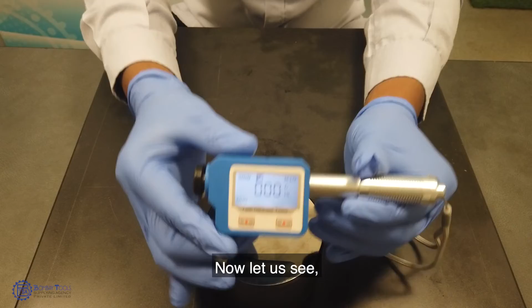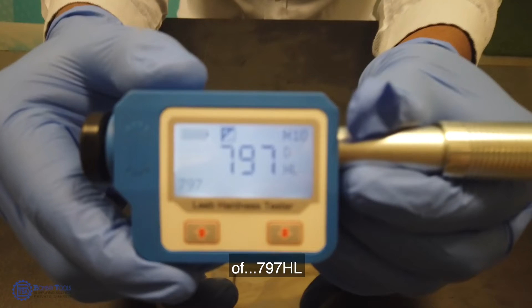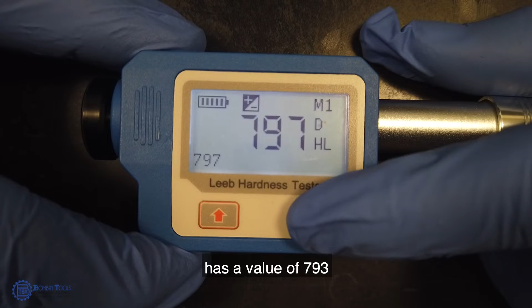Now let us see how to calibrate and use the instrument. We can load the carbide ball by pushing the loading device downward. Then place the instrument on the block and release it by pushing this button. We have got a reading of 797 HL. As our master block has a value of 793, we will adjust the reading to calibrate the instrument.